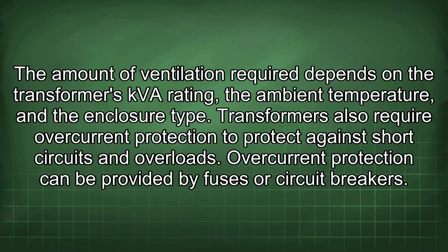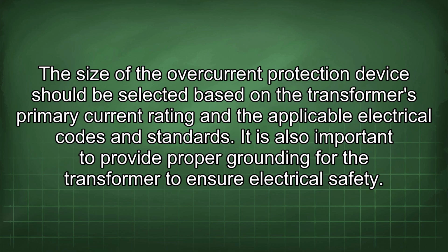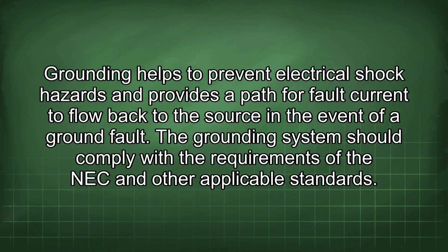Transformers also require overcurrent protection to protect against short circuits and overloads. Overcurrent protection can be provided by fuses or circuit breakers. The size of the overcurrent protection device should be selected based on the transformer's primary current rating and the applicable electrical codes and standards. It is also important to provide proper grounding for the transformer to ensure electrical safety. Grounding helps to prevent electrical shock hazards and provides a path for fault current to flow back to the source in the event of a ground fault. The grounding system should comply with the requirements of the NEC and other applicable standards.